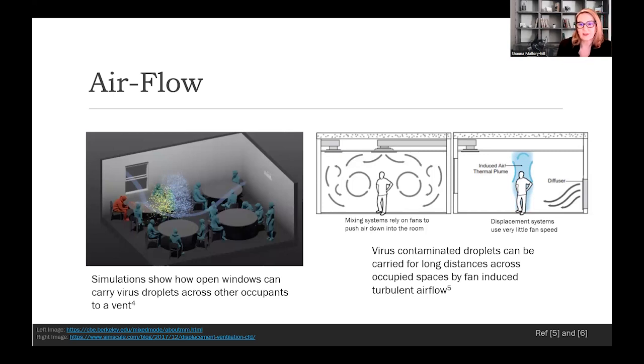So the thermal plume, or the heat of the person's body, naturally causes the air to come to the person and rises up the person's body. So it uses very low fan speed. You wouldn't even feel a draft with this kind of system, and therefore it's very ideal. It's kind of like filling up a pool of water and moving the contaminants out of the breathing space. So different kinds of ventilation systems, where you bring in the air low and you exhaust it higher, are quite good for limiting the infection across people within a room.